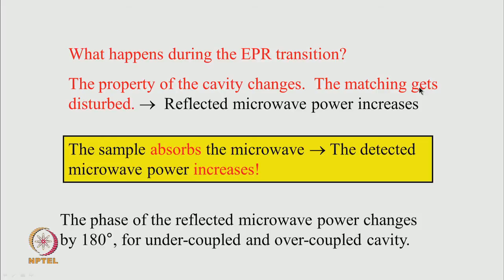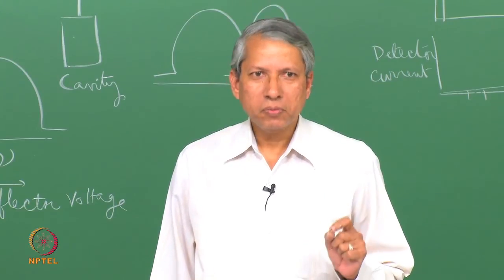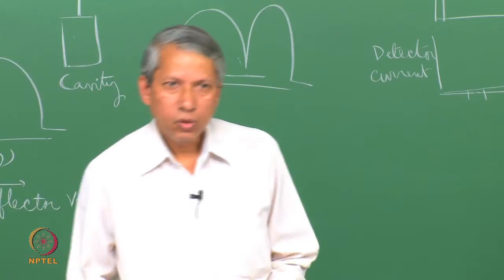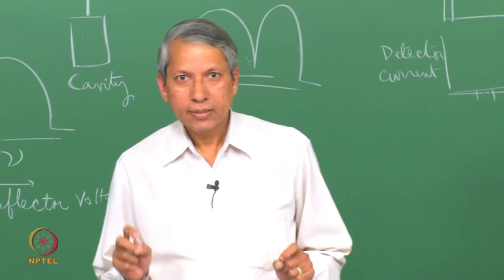Now, what happens during an EPR transition? The property of the cavity changes — the matching gets disturbed. Matching means that the reflection from the microwave cavity is very, very small, and that matching gets disturbed, so a little bit of microwave power is reflected. So this is a bit of a funny situation: when the sample absorbs microwave power, the detector actually sees more power falling on it. Unlike a conventional absorption spectrometer where the detector sees less power when the sample absorbs, here when the sample absorbs microwave, the detector sees more power, because the spectrometer is set up based on cavity matching such that very little power falls on the detector in the steady state where no absorption takes place.